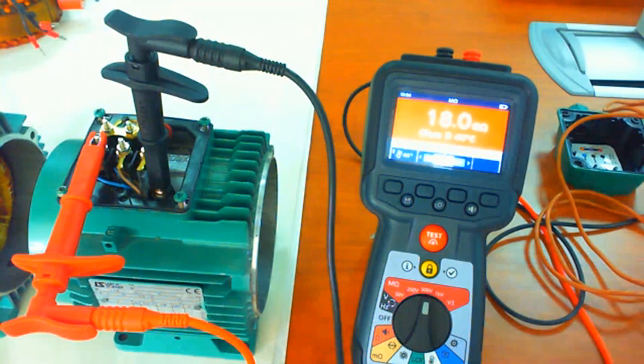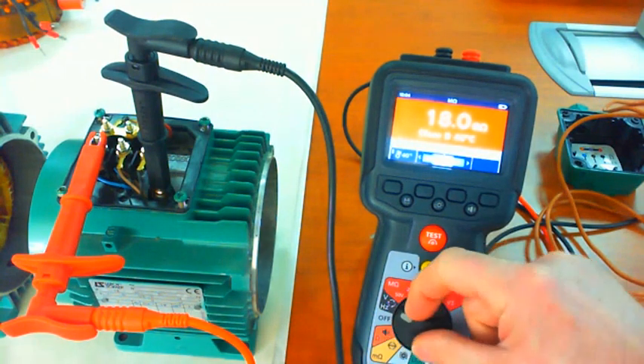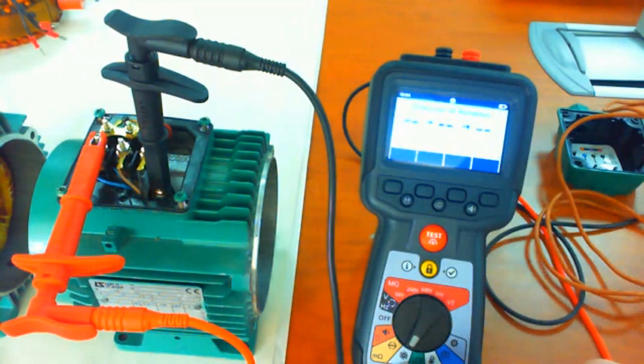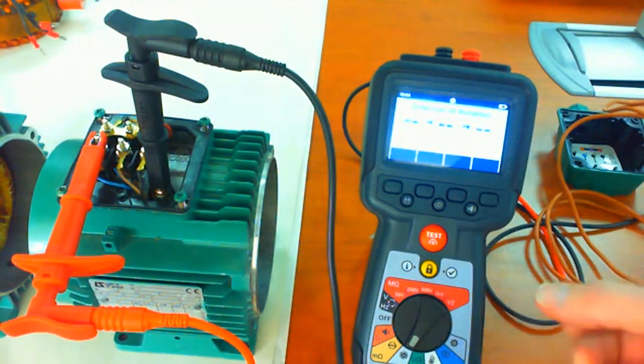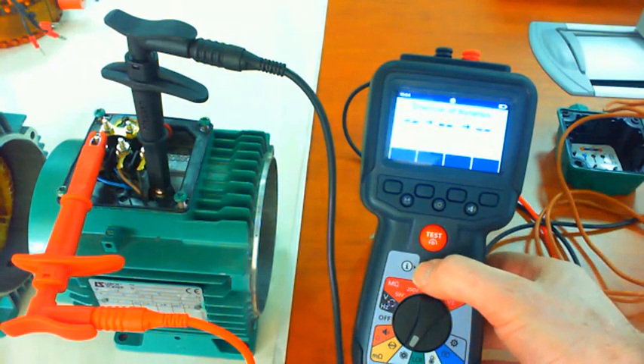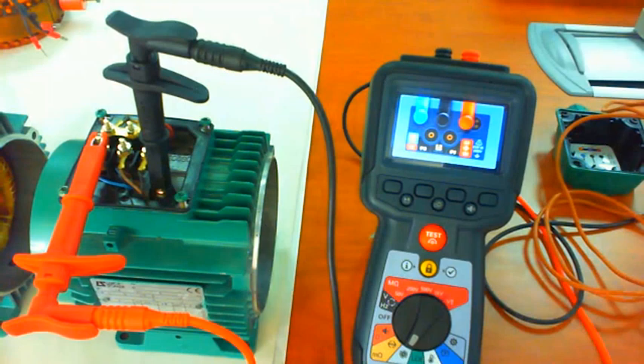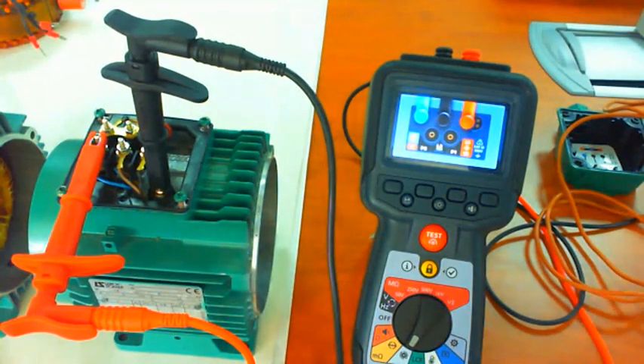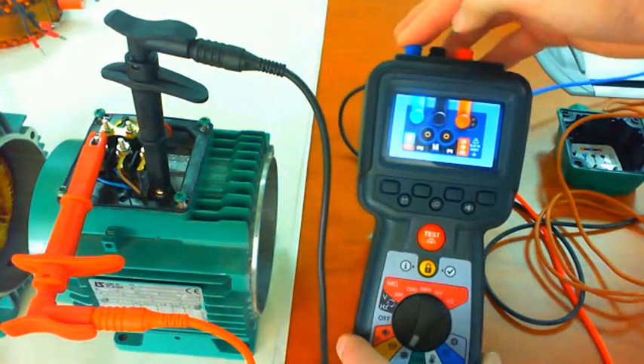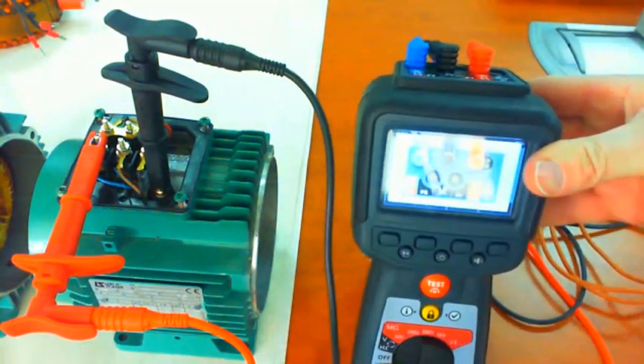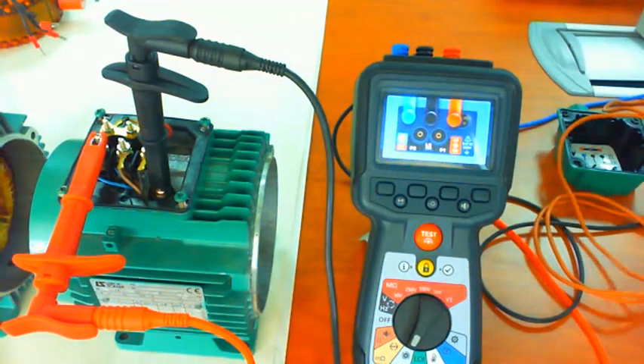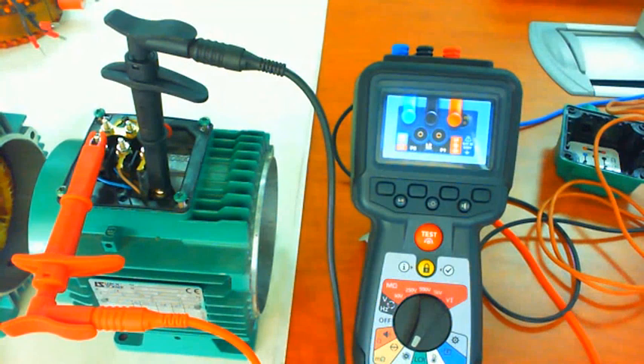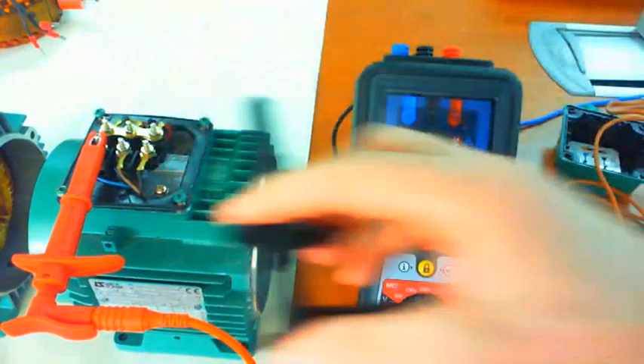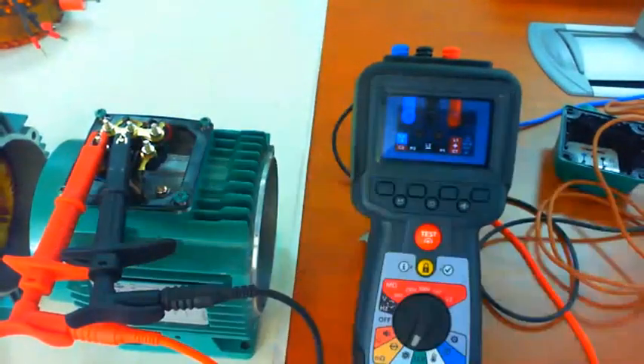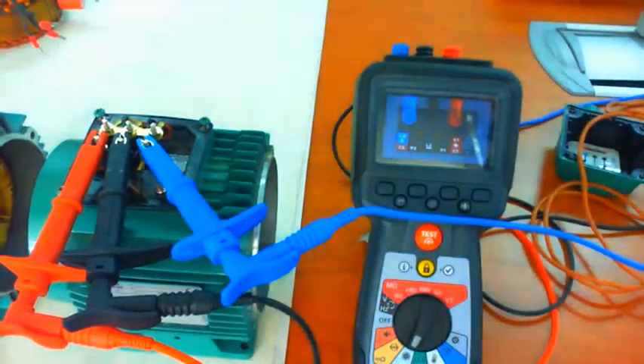Okay, and then the last test I want to show you is the motor rotation direction test. So this is a 3-phase test. We need to connect all 3 phases. So again, if you're not sure, press the lock button and it tells you how to connect the leads. I need to add my blue into the top. So we've now got red, black, blue. And I'm going to add... so the sequence is red L1, black L2, blue L3.